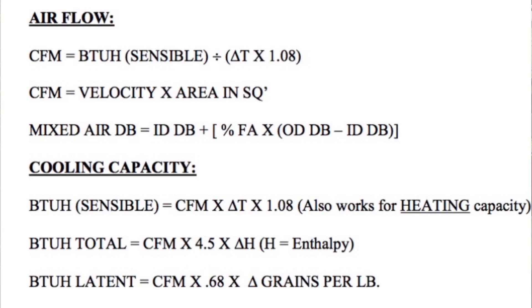At the very top, the airflow equation is: CFM equals BTU sensible divided by delta T times 1.08. Down at cooling capacity, the sensible cooling formula — with cooling you have a negative delta T and with heating a positive delta T going from return to supply. Look at BTU sensible: it's CFM times delta T times 1.08. It's pretty simple if you're working on something that doesn't produce any latent change.